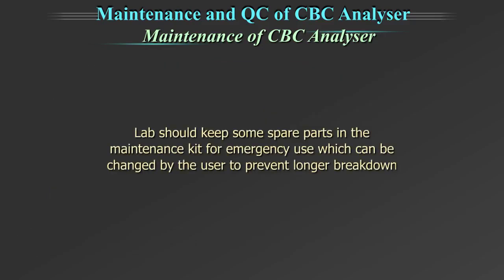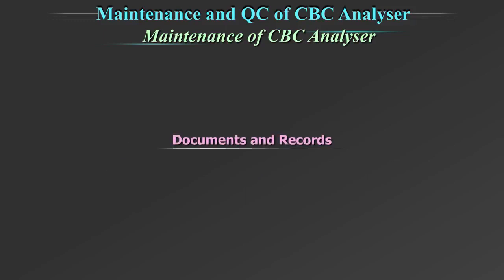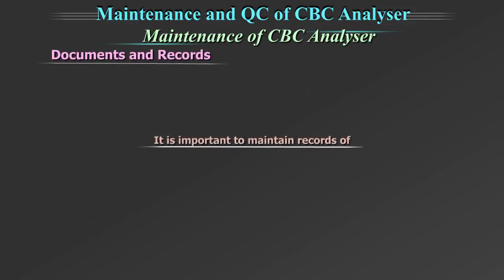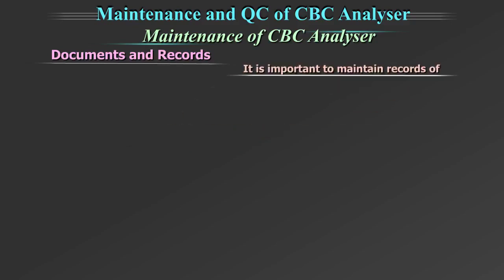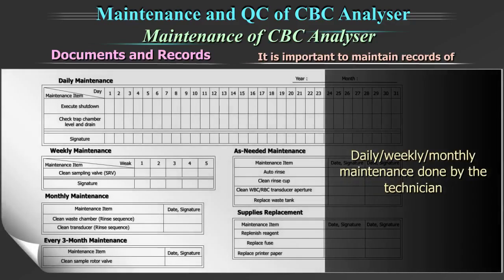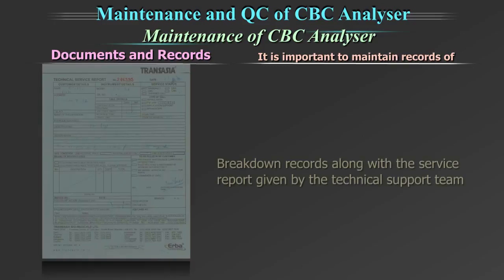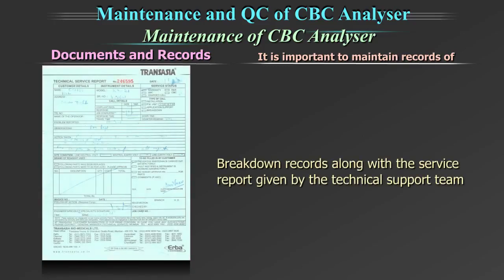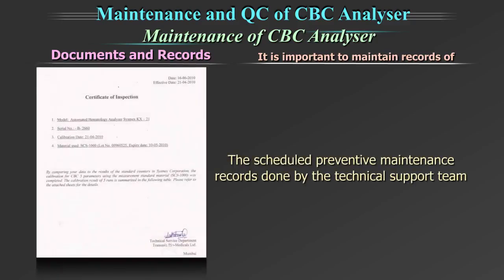The lab should keep some spare parts like fuses, tubings, etc. in the maintenance kit for emergency use, which can be changed by the user. This will prevent longer breakdown time. Documents and records. It is important to maintain records of daily, weekly, monthly maintenance done by the technician, breakdown records along with the service report given by the technical support team, the scheduled preventive maintenance records done by the technical support team.